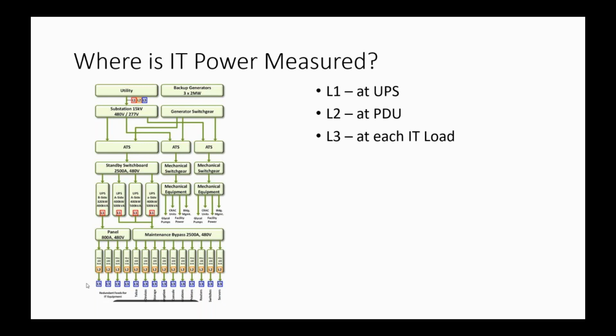Well, I have this conversation often, and it is funny that we've been talking about this, and a lot of the power measurements have been around for decades. But what folks need to understand is that the reason those power measurements have been around for literally about 20 years was to ensure that a system was staying within the power and thermal envelope of the enclosure where it was, meaning the rack or the rack circuits, or the cooling capacity of a particular device.